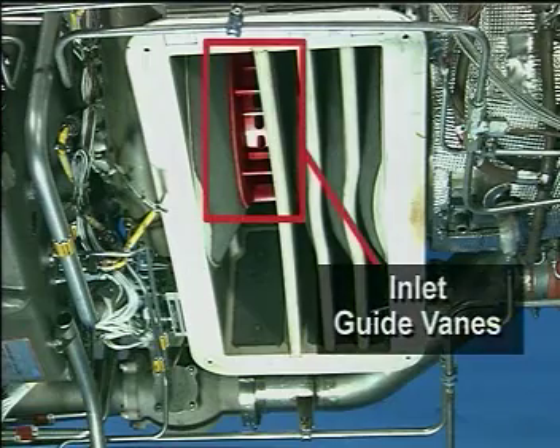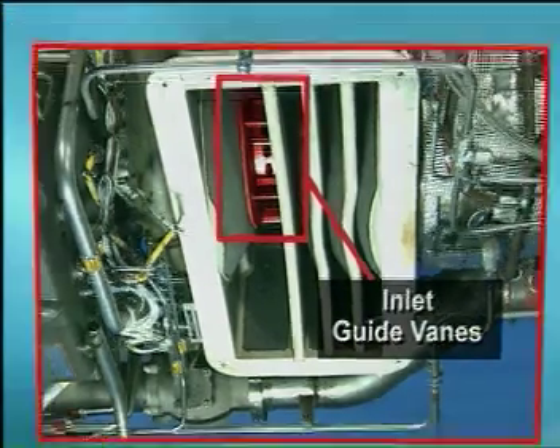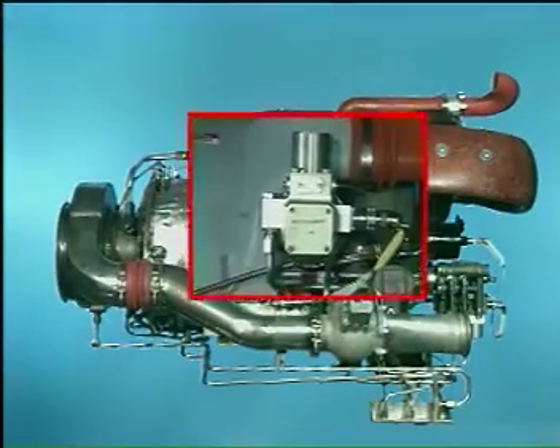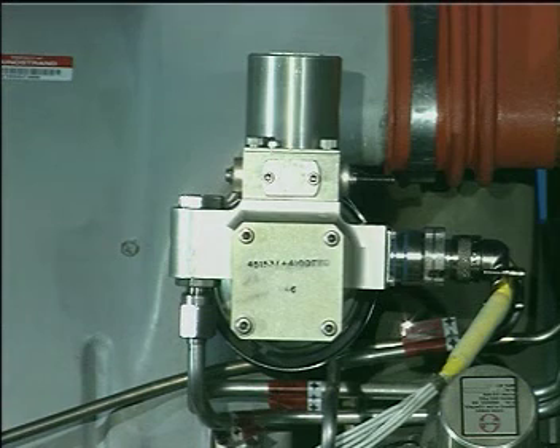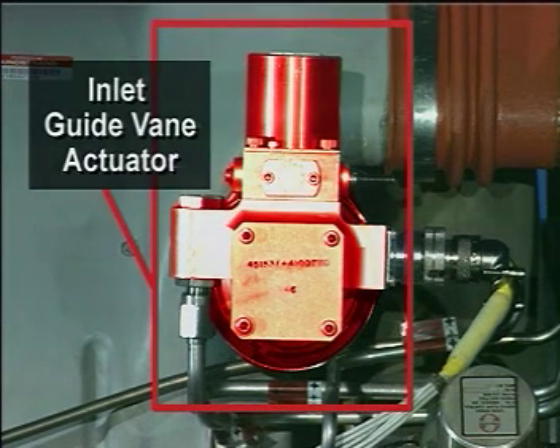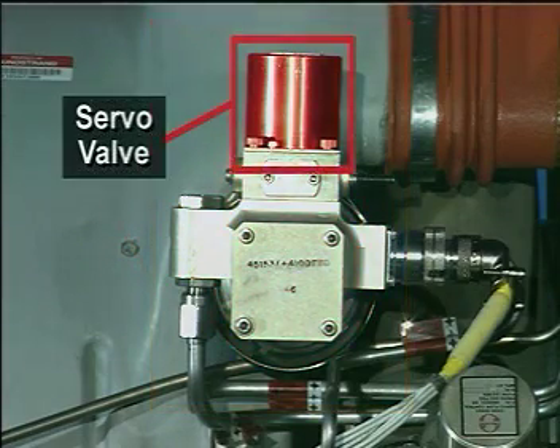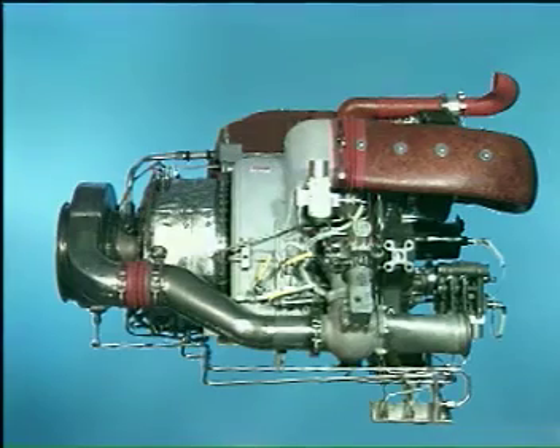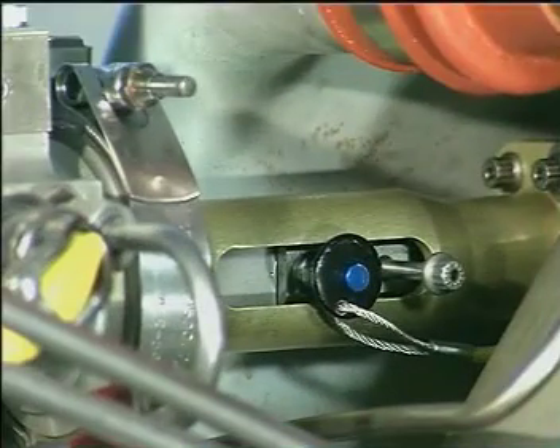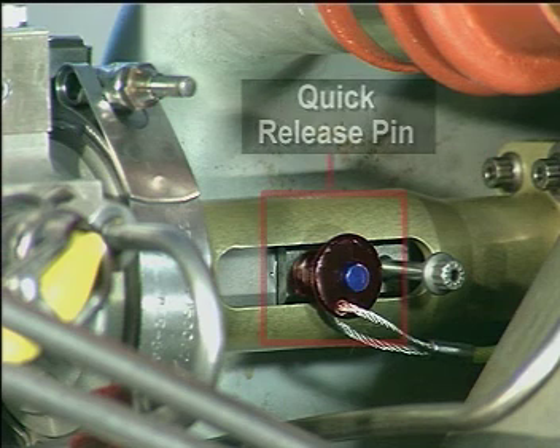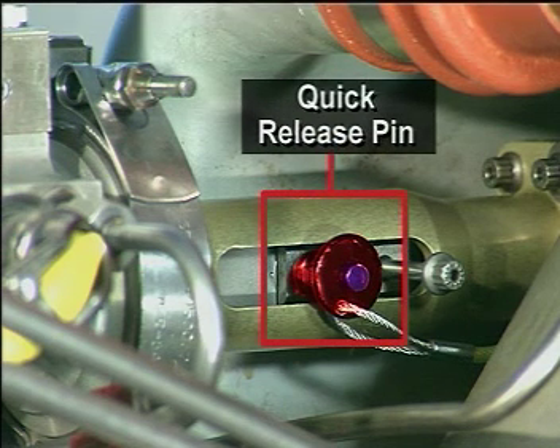The airflow to the load compressor is controlled by a row of internal inlet guide vanes. The inlet guide vanes are operated by the inlet guide vane actuator located at the 3 o'clock position on the load compressor case. The inlet guide vane actuator is operated by servo fuel supplied from the fuel control unit pressure regulator. It is controlled by a servo valve. The actuator is connected to the operating rod by a quick release pin. The inlet guide vane position is monitored by an internal linear transducer.